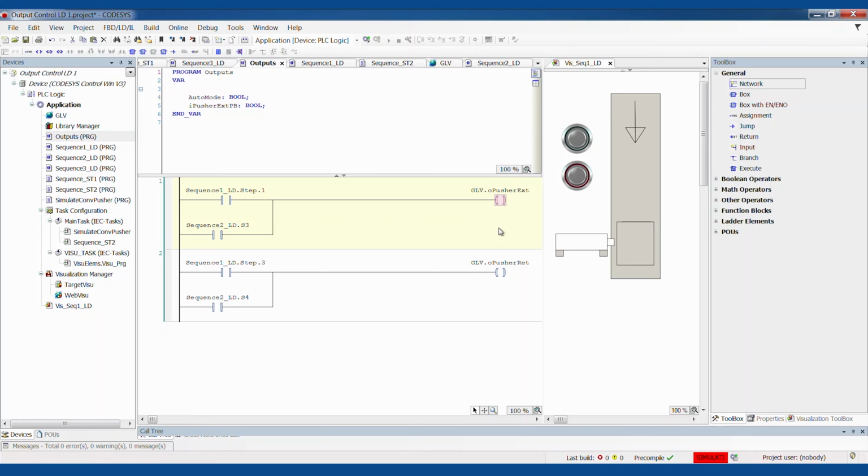But if they're fighting, probably one of the coils will get the piece moving, the pin or whatever it is, and will have that reduced current state. And the other solenoid is going to end up still at maximum current trying to pull that in. And while I haven't seen this happen personally, because we always put in some protection for that, it has been reported to burn out solenoids. And even if it's not burning it out, it's going to heat it up. And that's not really what you want.